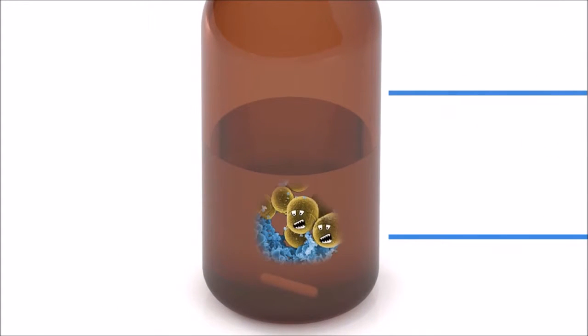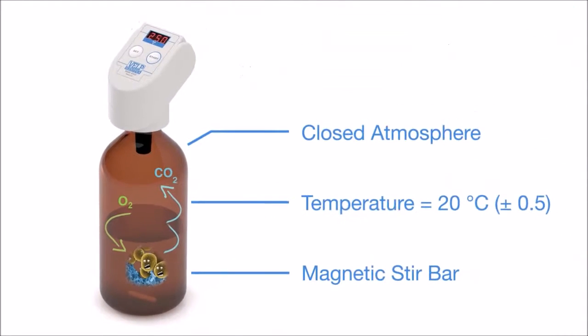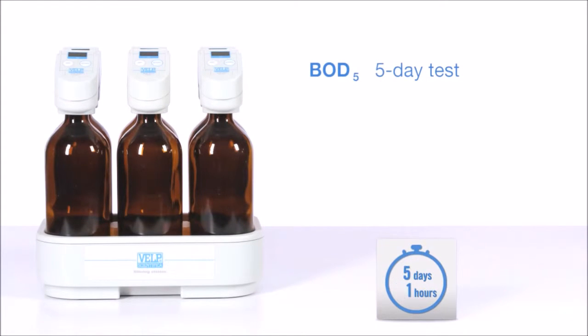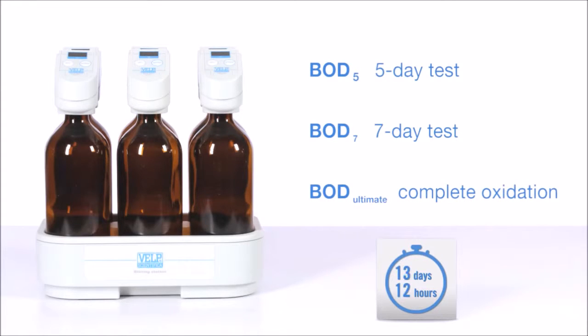The measuring principle consists of determining the oxygen concentration at the beginning and end of a measurement period. The typical analysis is BOD-5, a 5-day incubation test. Longer measurement times are also used, such as BOD-7, a 7-day test, and BOD-Ultimate for the complete degradation of organic substance.